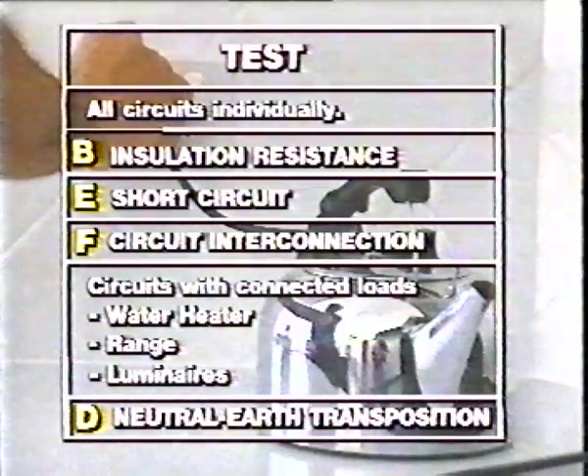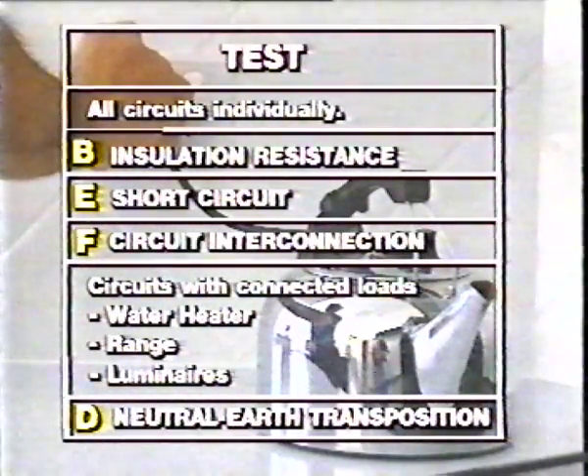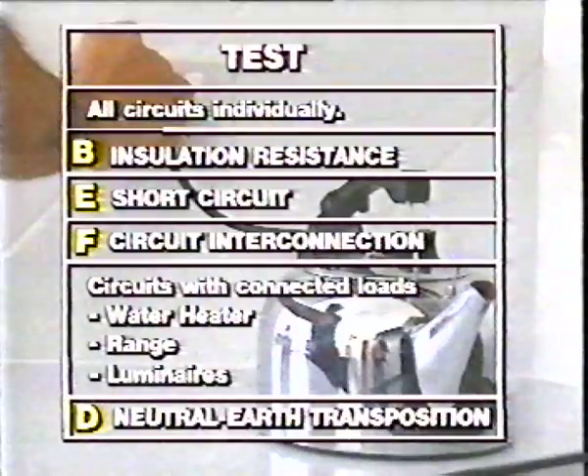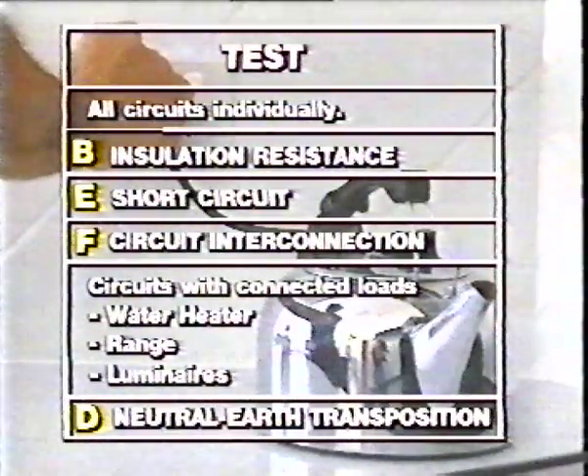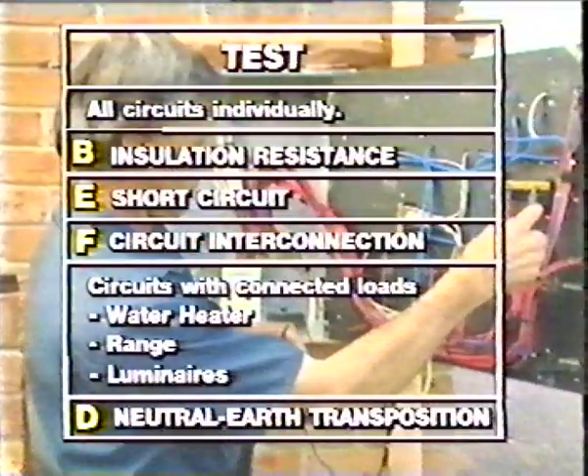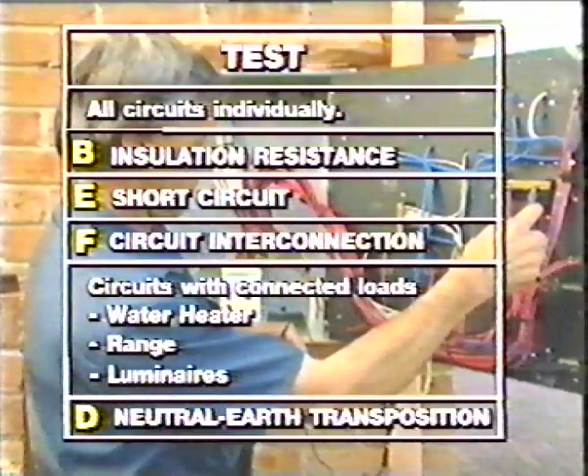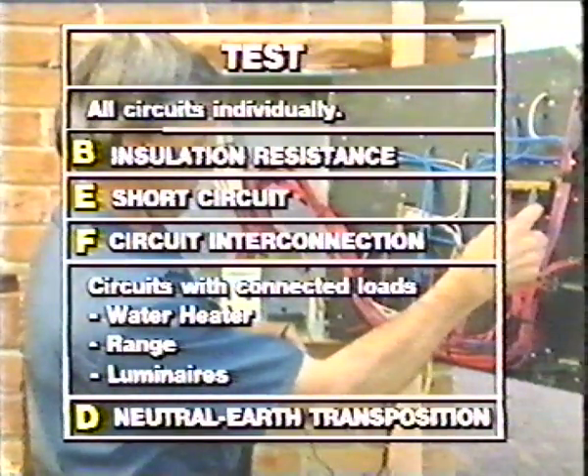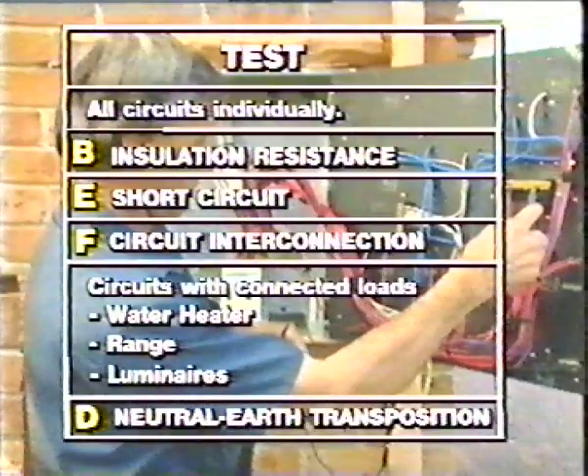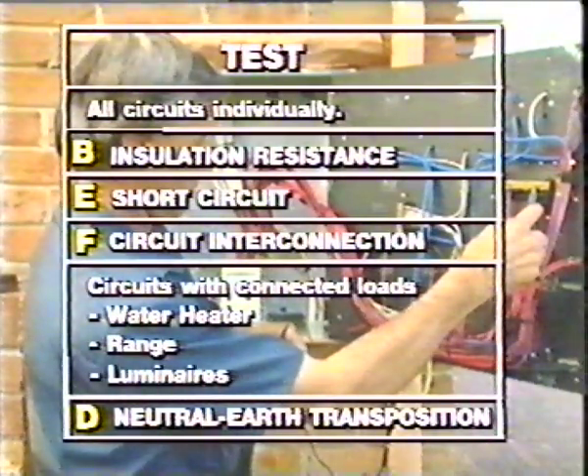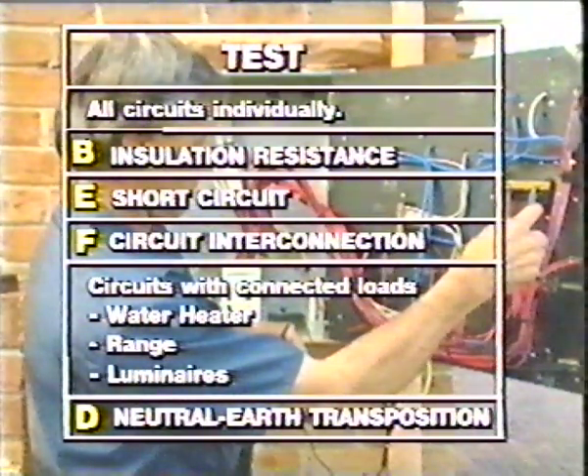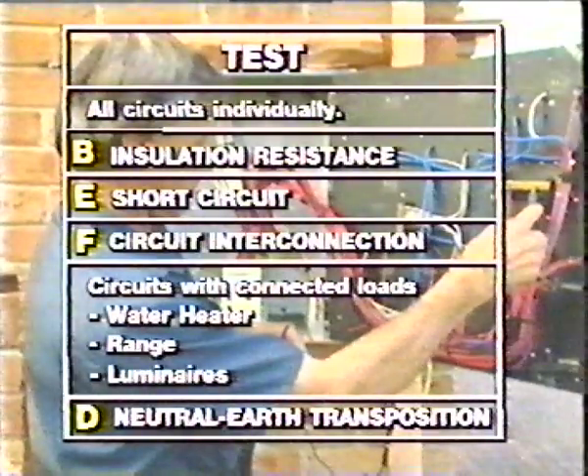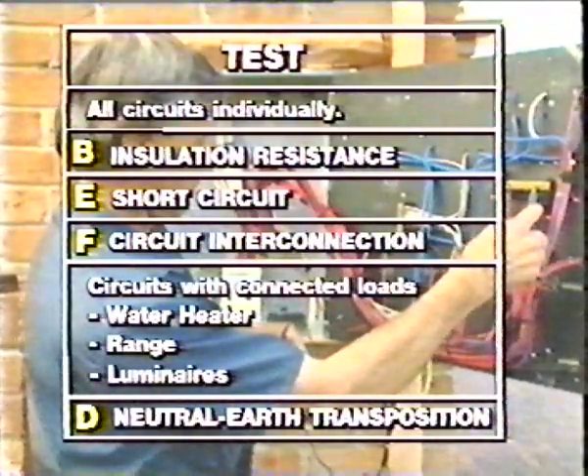Before commencing insulation resistance tests, ensure that all lighting circuit switches are closed and appliances are removed from general purpose outlets. Then test all circuits individually for insulation resistance as in test B. Remember that if multi-way switching is used in lighting circuits, these switches should be operated during the test to ensure that all conductors are effectively tested.